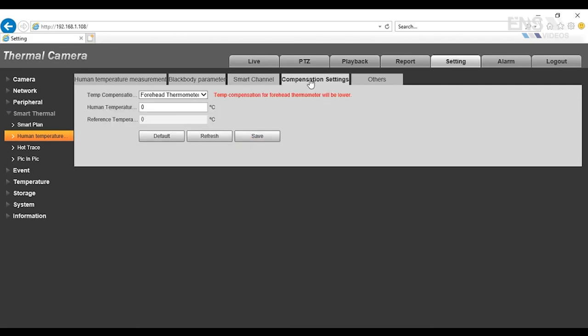For compensation settings, since we are measuring the forehead of the person that's walking to the camera view, then you want to select it to forehead thermometer and then hit save.